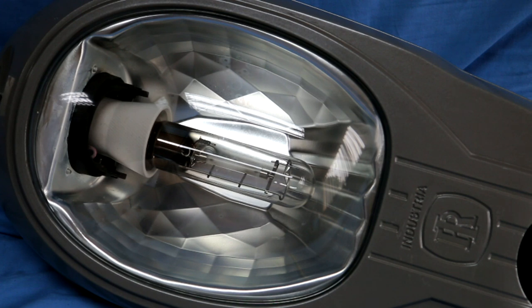The normal high pressure sodium I think it's only something like 20 percent color rendering. This is 65 percent, which is actually better than a few of the old halophosphate fluorescent lamps. There is a downside to this, the luminous efficiency is slightly lower and it takes quite a while to warm up.